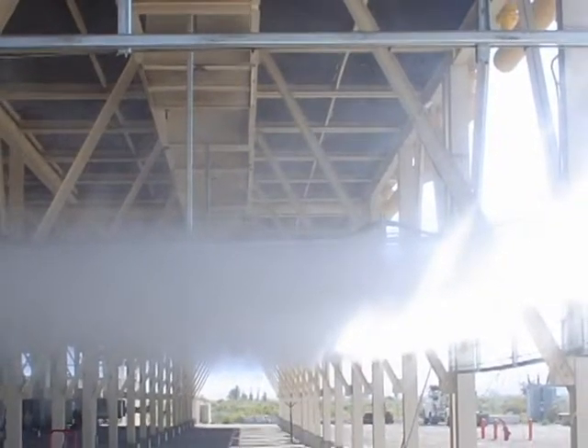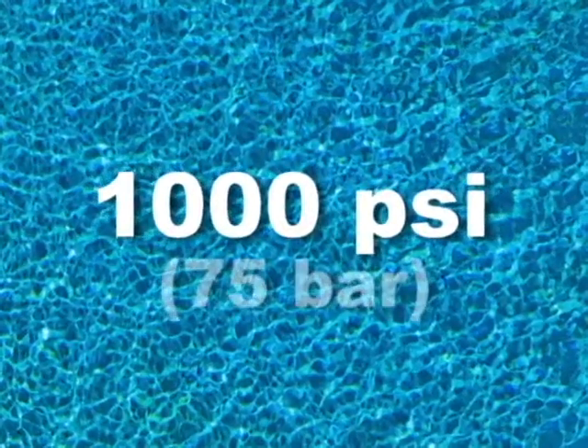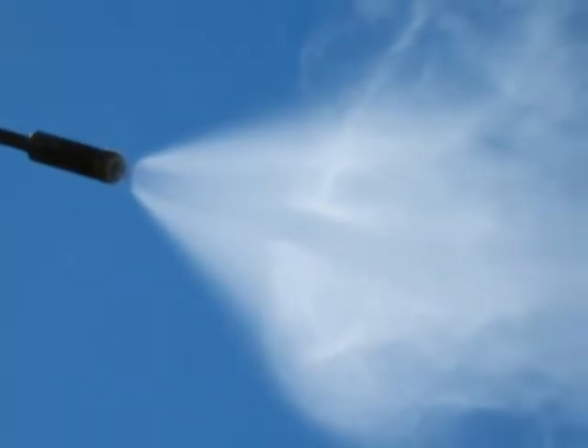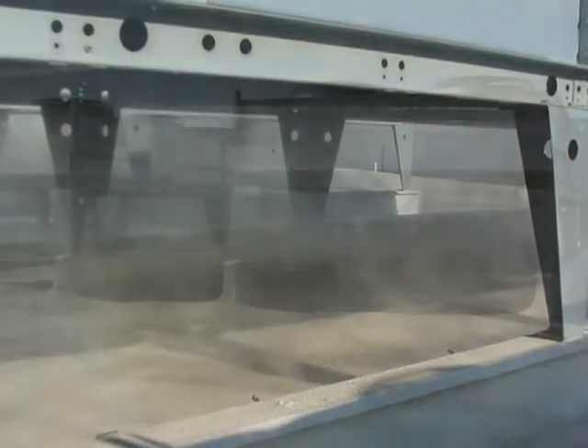Using Micro-cool industrial high-pressure pumping systems, water is pressurized to over 1,000 PSI or 75 bar and is forced through patented nozzles to create a 10 micron spray that flash evaporates, extracting large amounts of heat from the air.